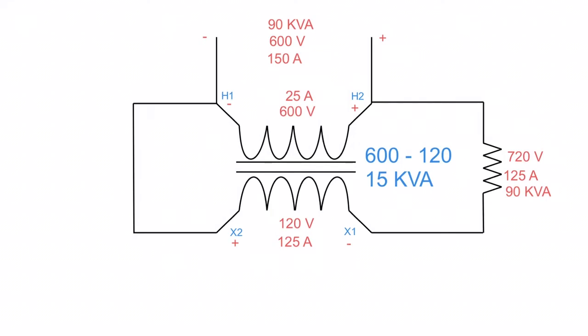This is a boost connection, where the flux is boosting to give an overall voltage of 720 volts — the voltages add together. Notice that for the boost connection, 25 amps plus 125 amps gives us 150 amps, which is a good way to double-check. The same approach works for a buck connection: 25 amps minus 125 amps gives the 100 amps we calculated before. That's a great way to verify your work.